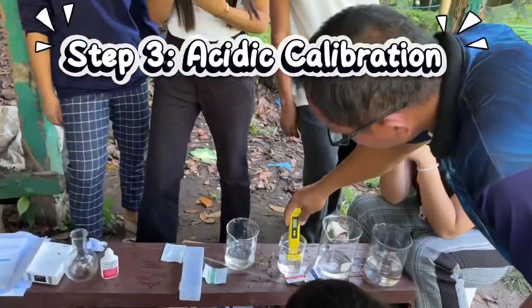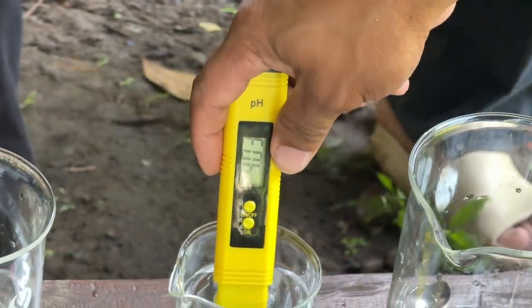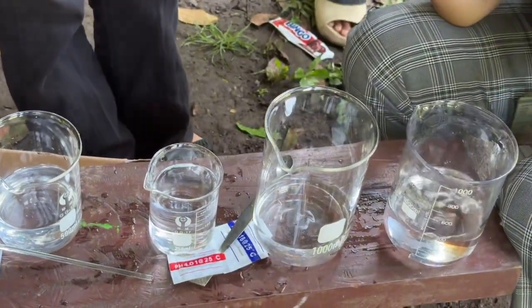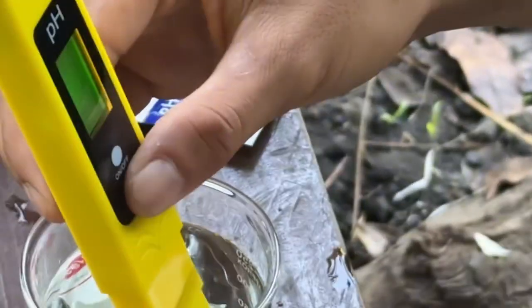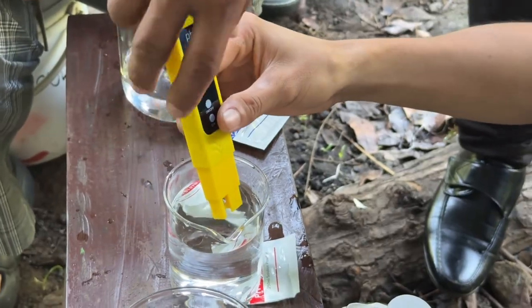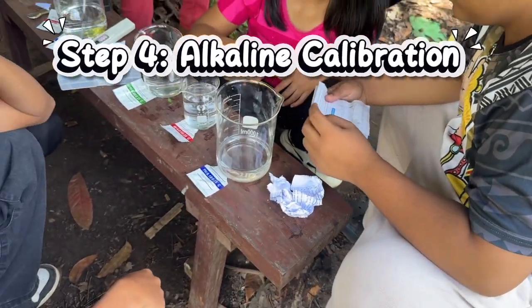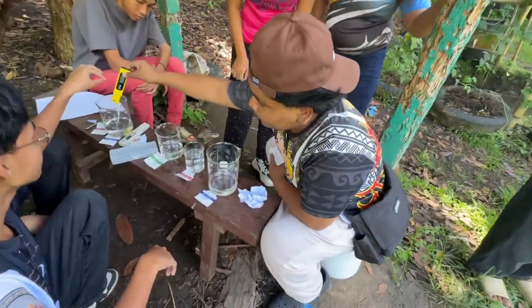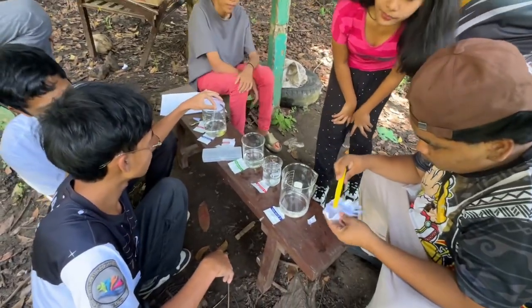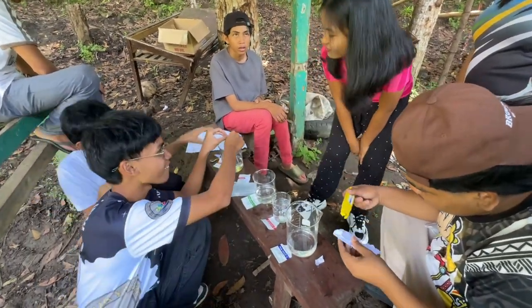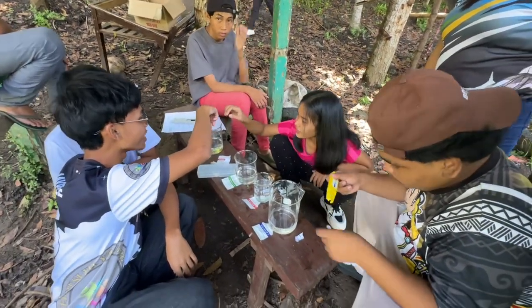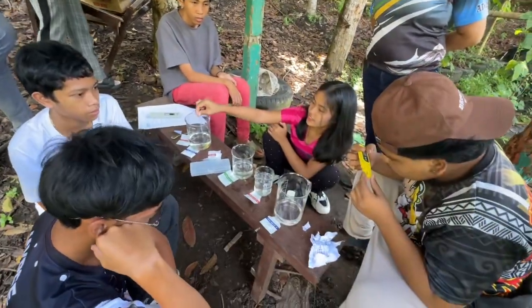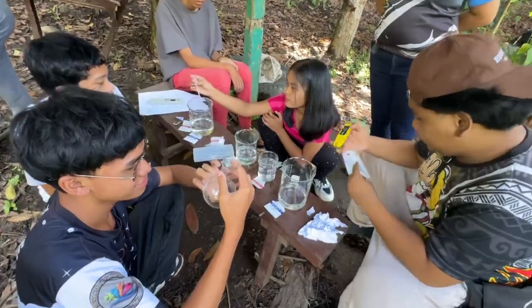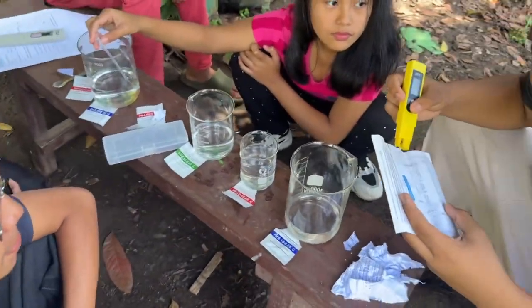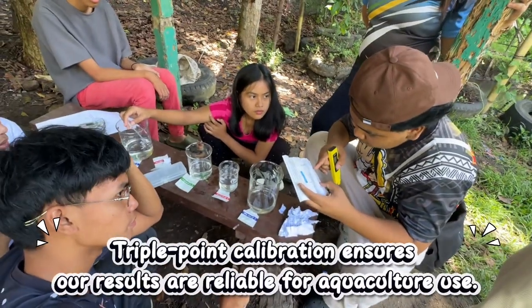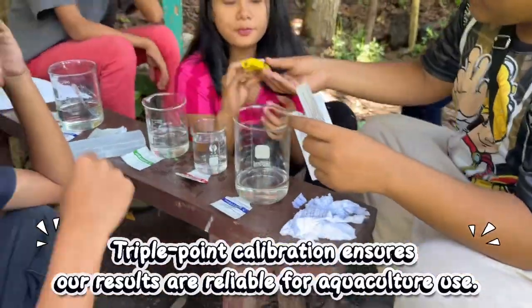Step 3. Acidic calibration. Red. Rinse the probe, then immerse it in the pH 4 buffer. Again, check the corrected value if the buffer isn't at 25 degrees Celsius. Alkaline calibration, blue. Step 4. Finally, calibrate using the pH 9.18 buffer. Once all 3 points are set, the pH meter is fully calibrated and ready for accurate measurement. Triple point calibration ensures our results are reliable for aquaculture use.